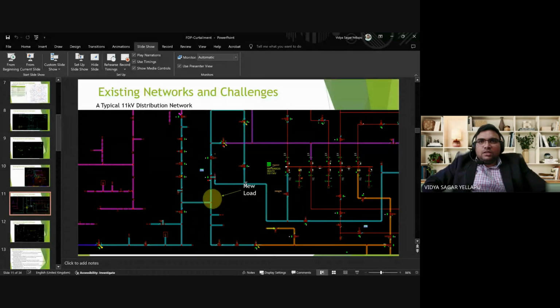In this case, if there is a fault here, the major concern for any network operator is to give continuity of supply. So this particular portion has to be immediately isolated from the rest of the network. One, two, three, four, all these open points and closed points are operated. Then this particular section of the network is isolated, and the rest of the network is given supply. Because of this new load, some sections of the network may get overloaded, and those sections are to be reinforced. That is the approach followed by the DNOs.